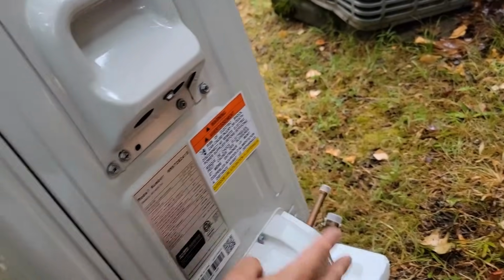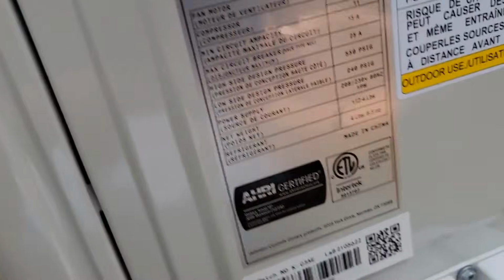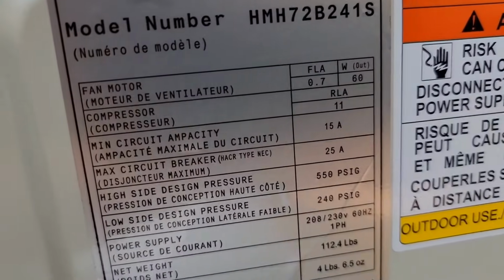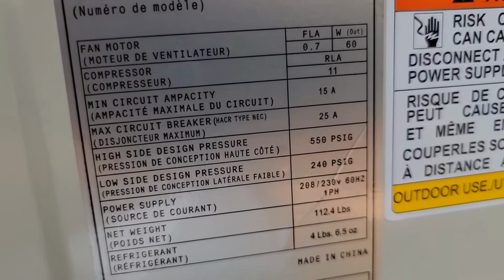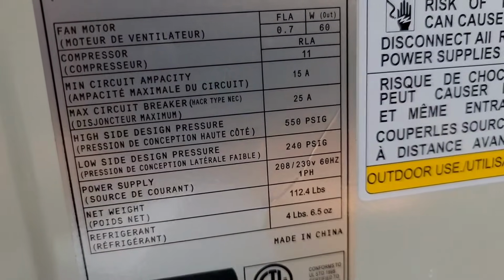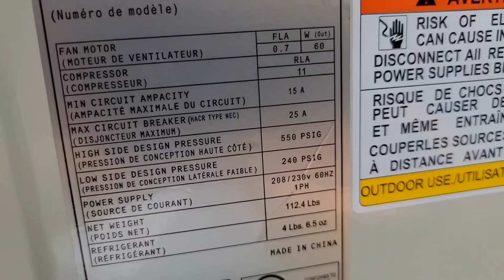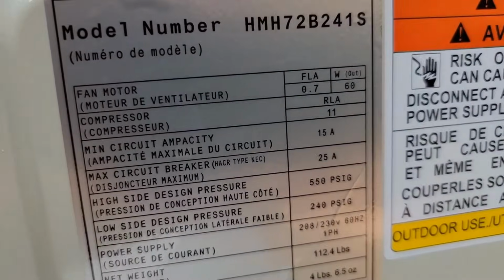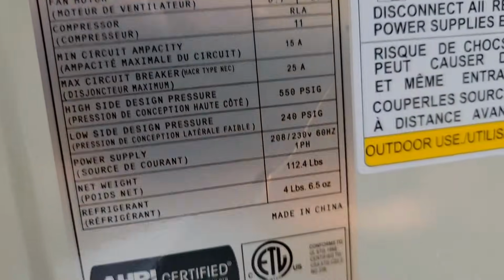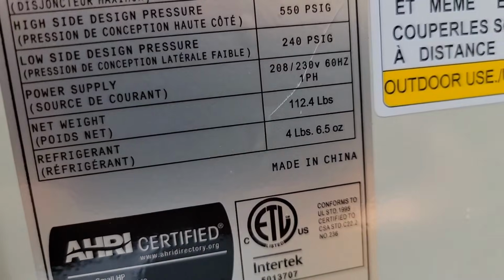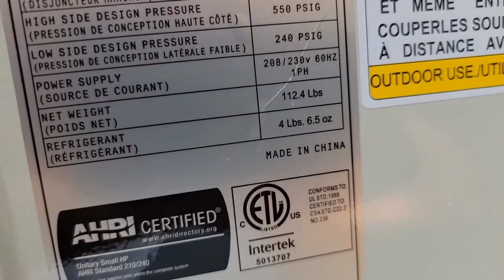So we'll need to take these two panels off here. It says for this 2-ton unit, because this is a 2-ton unit, that our max circuit breaker should be 25. So 25 double pole breaker, 230 volt unit. Minimum circuit amps is 15. And then it holds 4 pounds and 6 ounces.